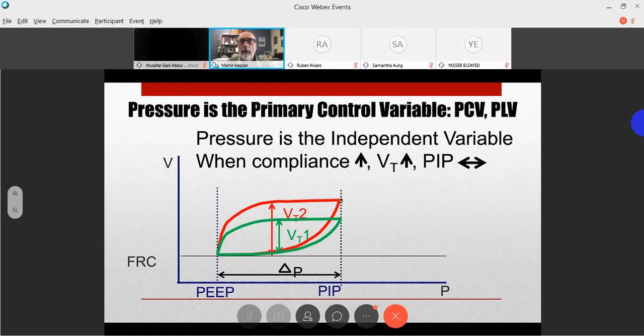So volume-controlled ventilation, I mentioned we tried to use early on. The problem with volume-controlled ventilation is that what is controlled is the volume delivered into the proximal end of the ventilator circuit over here. And that's all okay if you have a large patient whose lung volume is much larger than the circuit. There will always be some stretching of the elastic circuit and, more importantly, compression of gas within that circuit when you apply pressure.